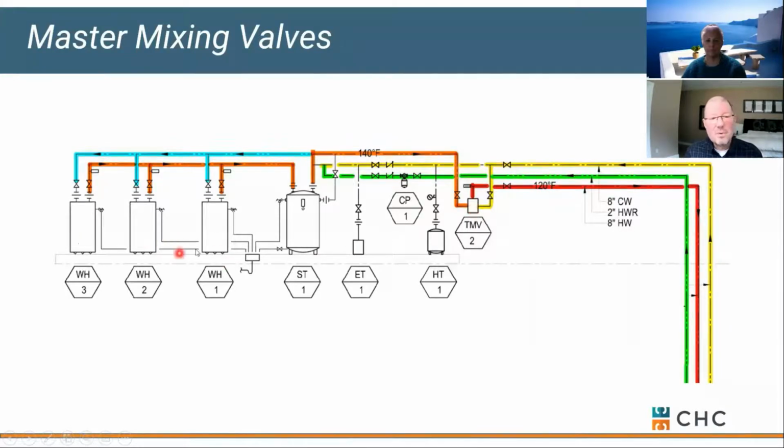On this other side, we've got water heaters, and I call each one of these 1,000,000 BTUs, but all they're doing is circling back and forth to this storage tank to keep it at 140 degrees. So the advantage of a highlighted drawing or flow schematic in this case, when somebody's using water, it's an open system, which means we're flowing water through our city line.